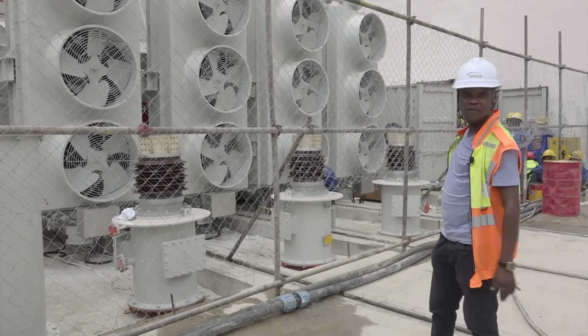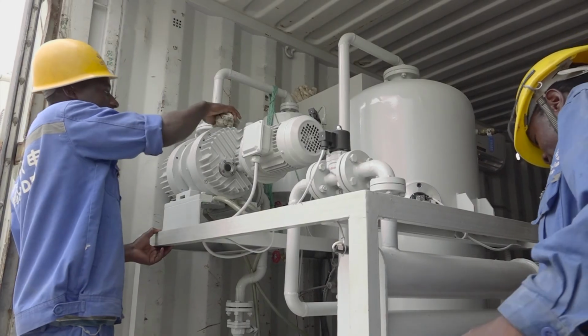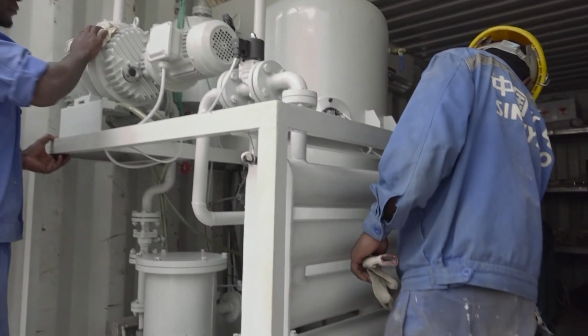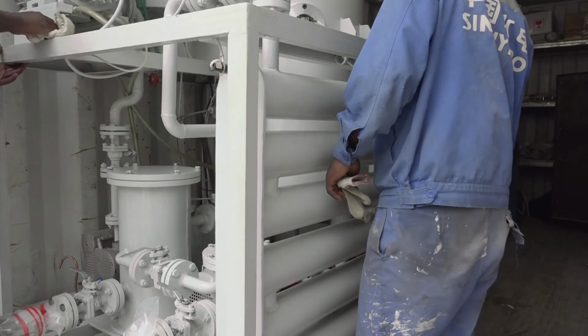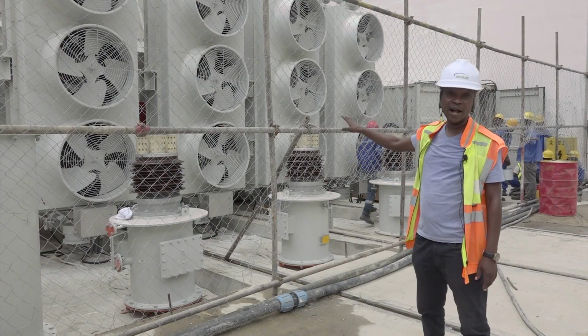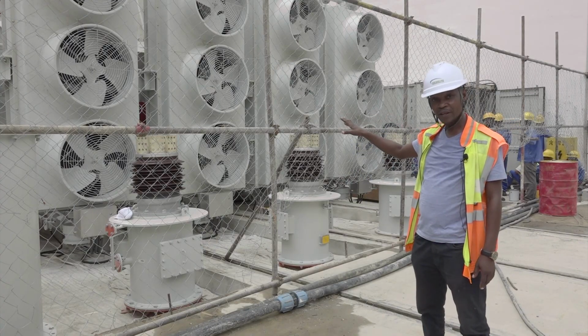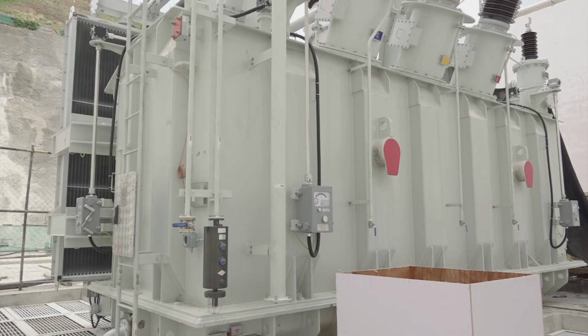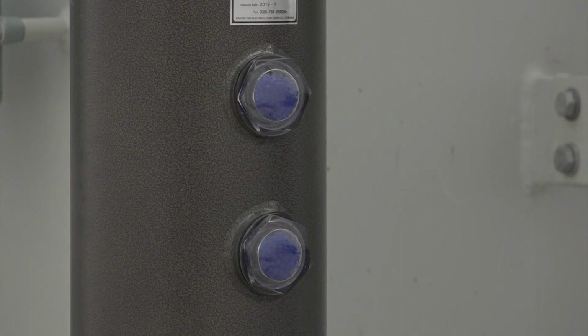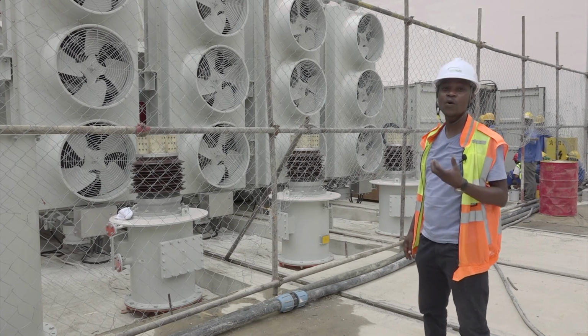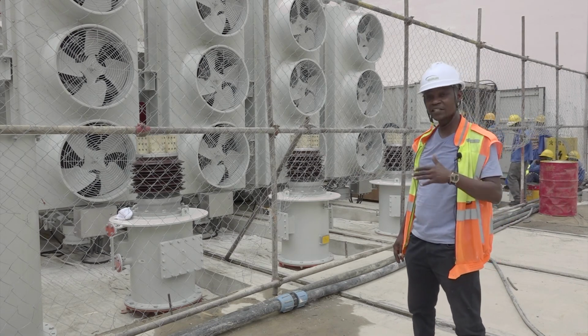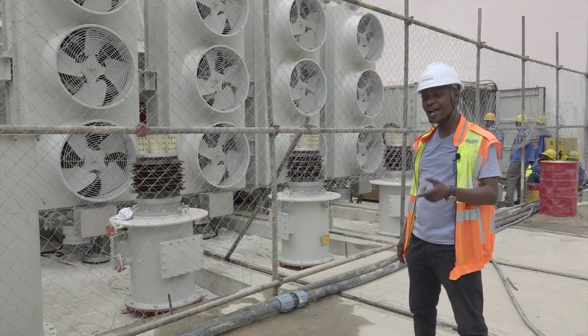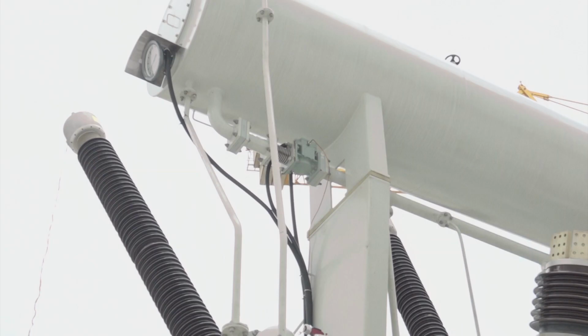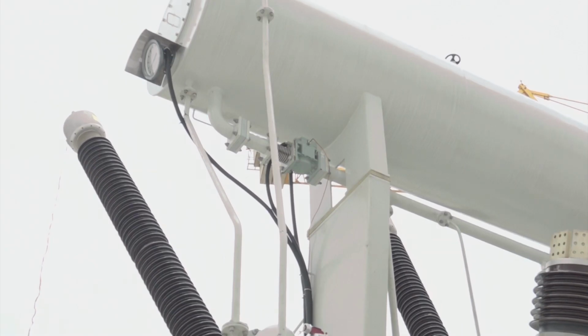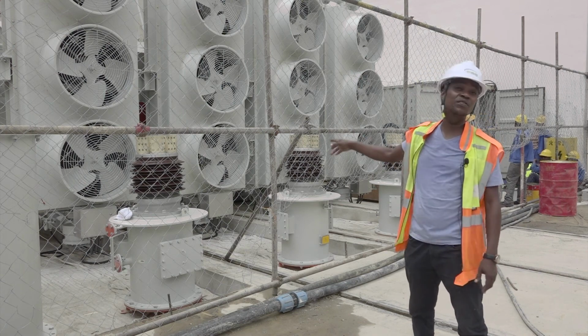What you are seeing over there is my colleagues preparing the oil filtering machine, because this transformer will be filled with oil. We must make sure that the oil is clean and of a certain quality. So to achieve that, we need to filter and clean the oil to remove moisture or any foreign particles, because those can cause short circuits in the transformers.